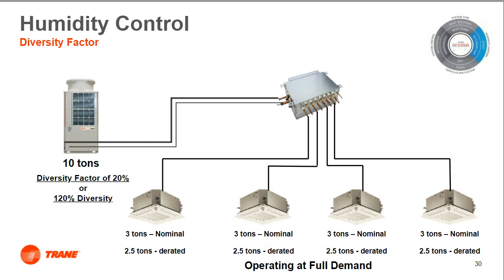Designers should also consider that outdoor air loads may not vary too much throughout the day, so caution should be taken when applying diversity factors to a VRF system, especially if you're using an LEV kit with a DOAS air handler unit connected to the comfort cooling system.